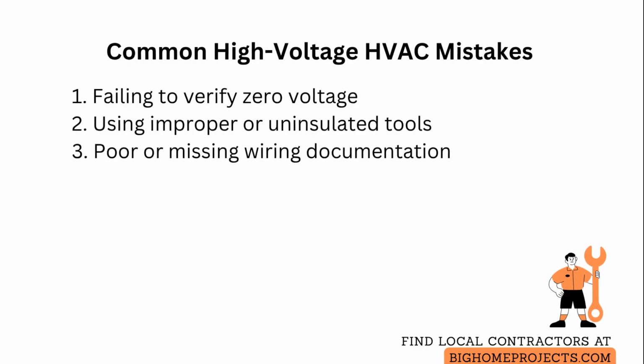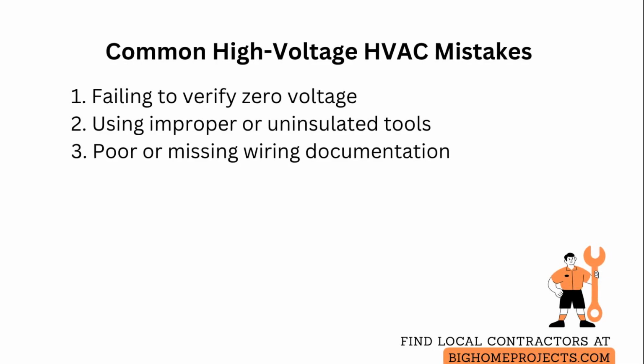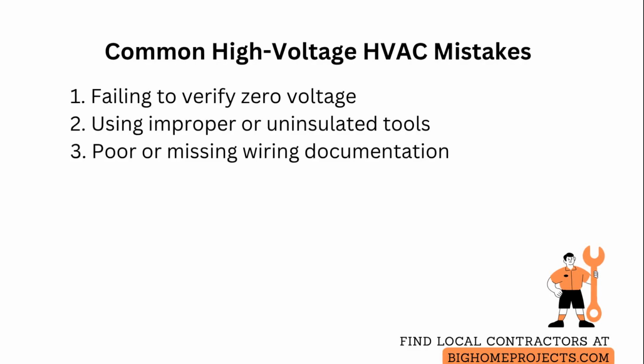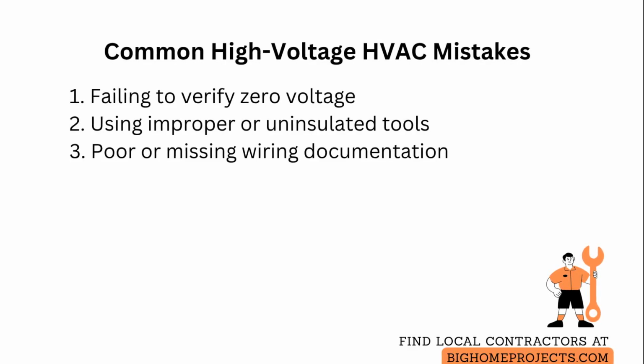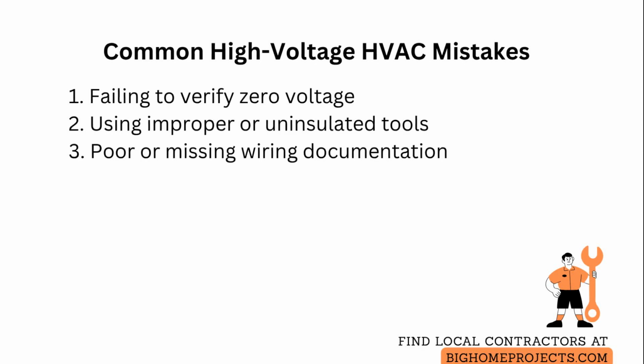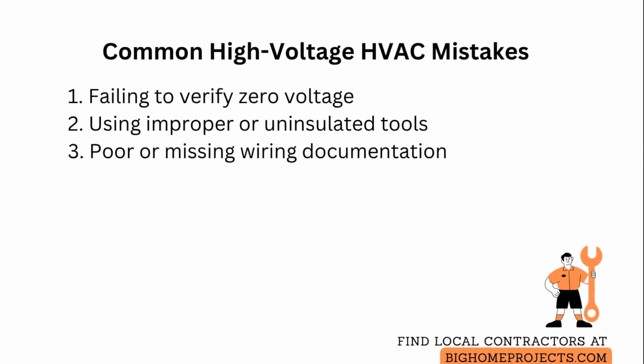A third common problem is poor documentation of wiring when disconnecting, which leads to miswiring on reconnection. So mark conductors, take photos, and label terminals before you disconnect anything.